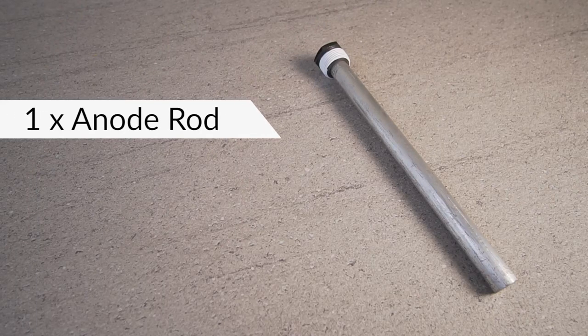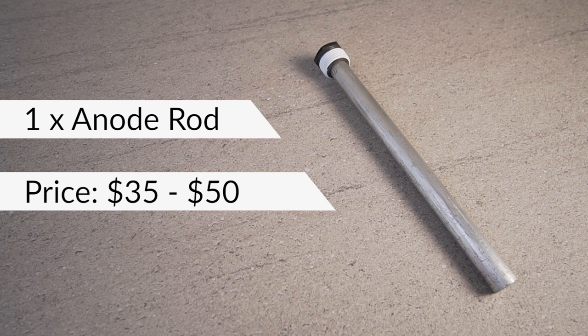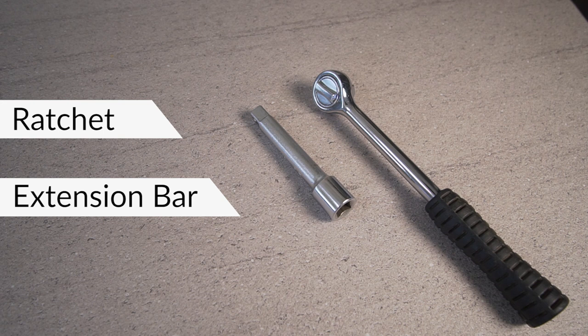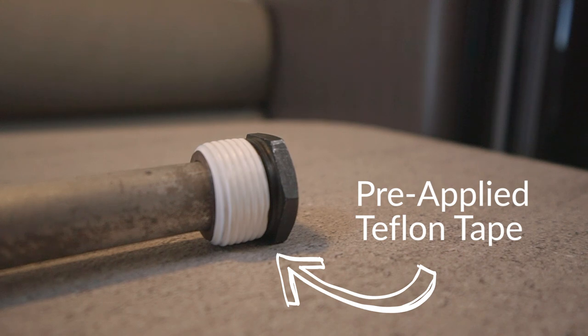First things first, we're going to need a new anode rod. These range online for anywhere from $35 to about $50 — the most expensive one I saw. This one I bought from RV Mega; it's a Camco branded one and it was $35. What I like about the Camco branded one is that the thread at the end comes pre Teflon taped, so you don't have to buy additional Teflon tape. You're also going to need a ratchet handle, a little socket extension bar, and a 27 millimeter socket or one and one sixteenth of an inch. If you don't buy an anode that comes pre-taped with Teflon tape, then you're going to need a small roll of Teflon tape as well.